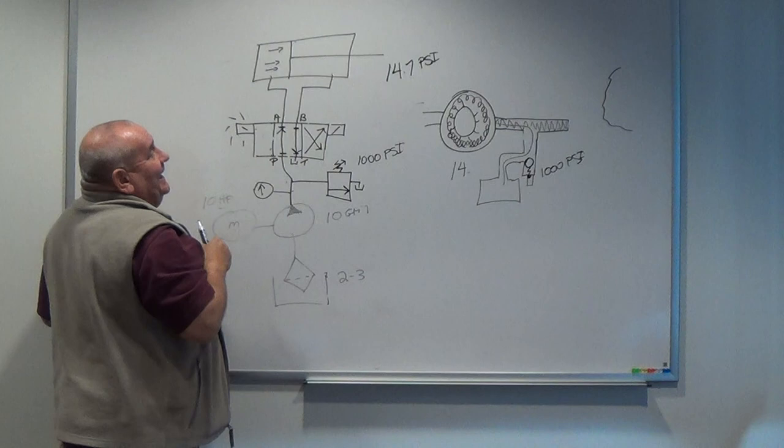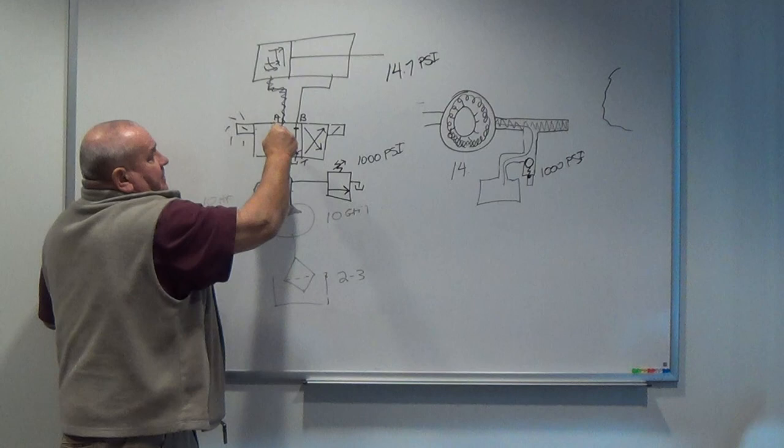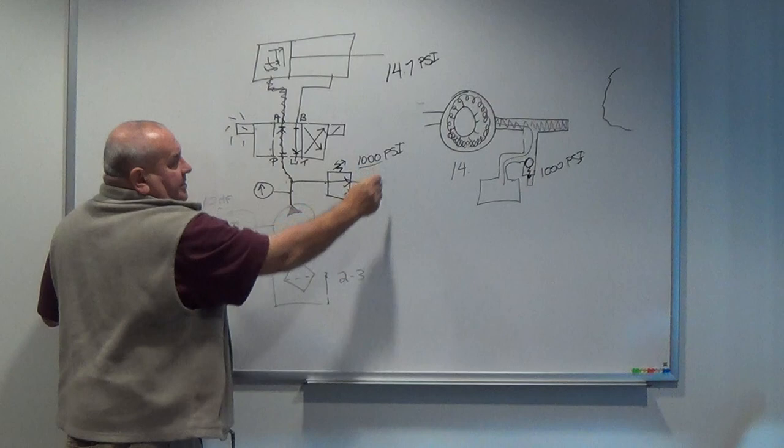So my flow is coming through here, my cylinder extends. At the end of my extension stroke, pressure begins to build. It builds down in through here. It's going to build over here into this chamber. This unit will now open and it will dump at 1,000 psi. So I can do a certain amount of work with that particular setup.